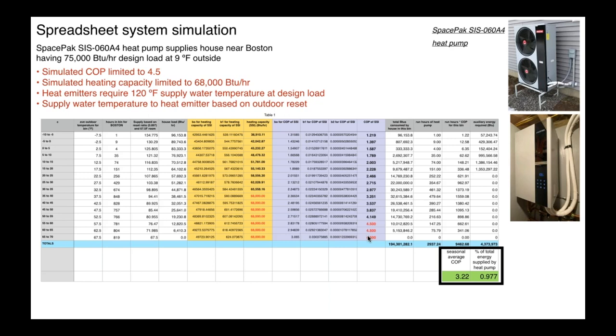Now, I'm estimating that. The manufacturer might be able to refine that a little bit better, but 4.5 is a pretty good COP on any heat pump. I'm also limiting the output to 68,000 BTUs per hour. In theory, those capacity curves would go higher. So you can see over here, we're limiting at 68,000. Again, a quick reminder, the heat emitters need 120 at supply, our supply water temperature at design load. And the supply water temperature to the heat emitter here is being reduced based on outdoor reset. So we're taking advantage of that condition where the outdoor temperatures are moderating and we're lowering the water temperature the heat pump is operating at. We're still maintaining comfort in the building, but we're not forcing the heat pump up into conditions that are unnecessary given the outdoor temperature to maintain comfort.